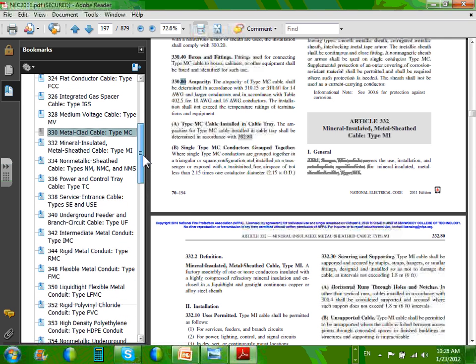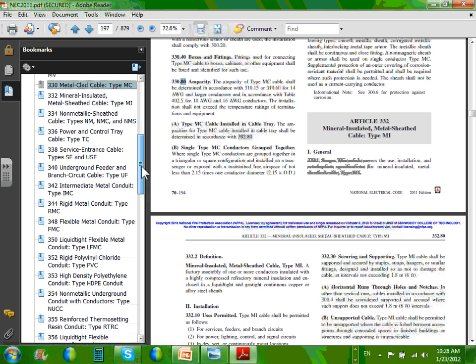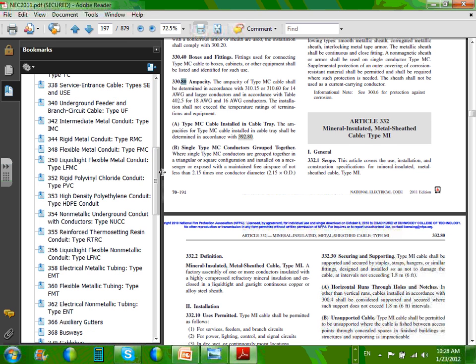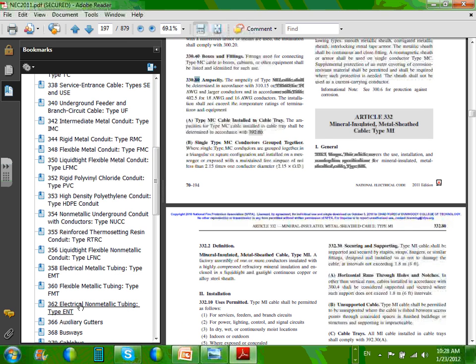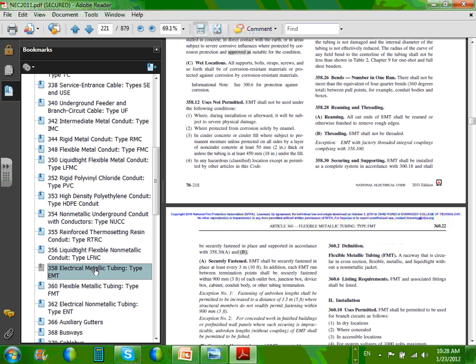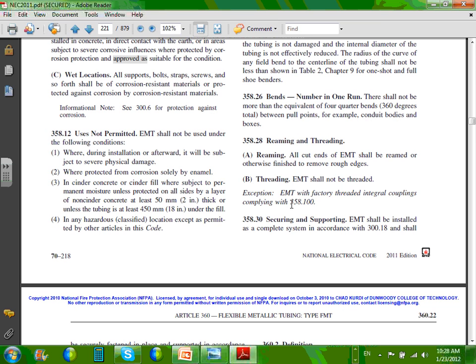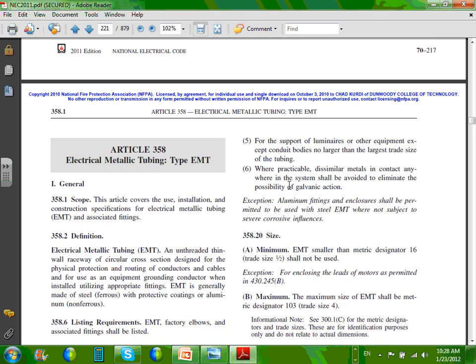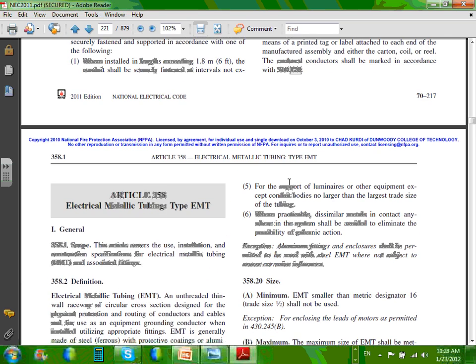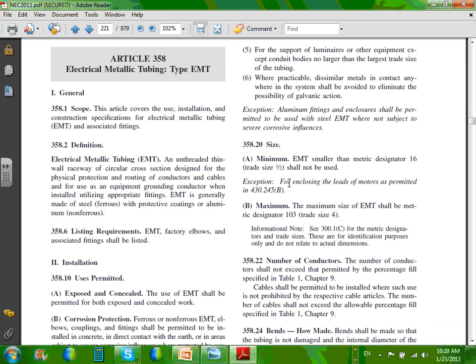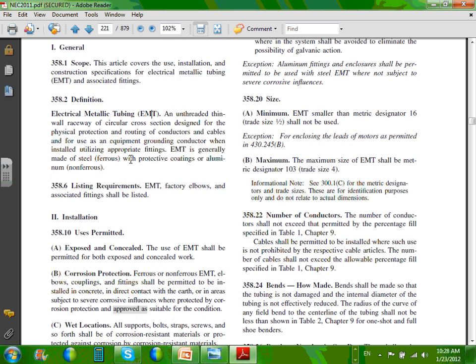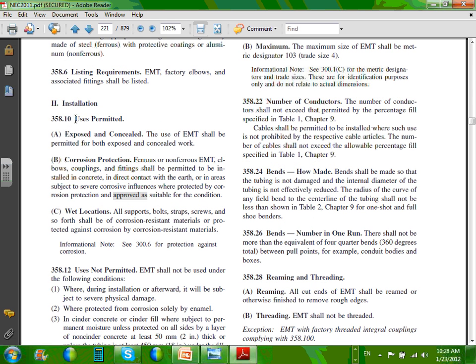Let's go to MC, EMT conduit. Help me here, EMT conduit. EMT, right here, 358, EMT conduit. If you go to the article on EMT conduit, this will be in yours, page 218. They describe it as thin wall conduit, round, and so forth. Uses permitted. Here's my favorite: you can expose that baby or conceal it.